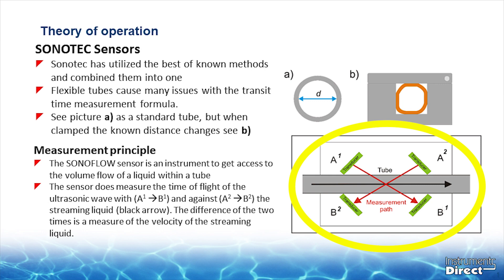At the same time, A2 sends a signal to B2. But in this case, the signal is going against the flow current and would take a longer period of time to transit the tube. The difference in transit time between the upstream and the downstream is proportional to the average flow velocity. And since we know the area of the tube now, the volumetric flow is calculated in engineering units.